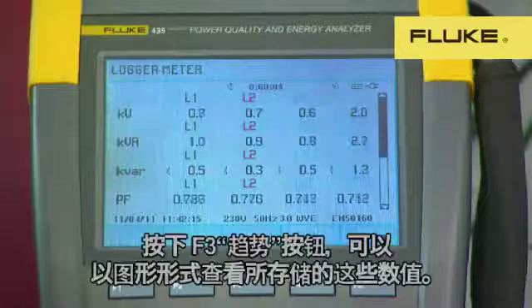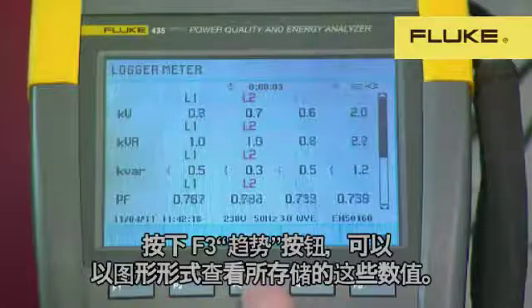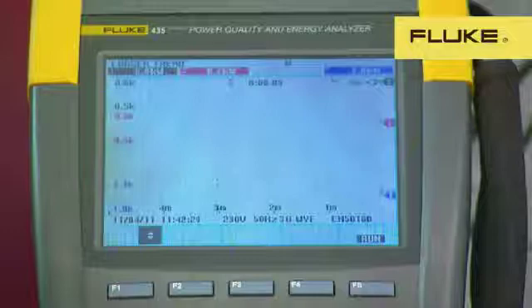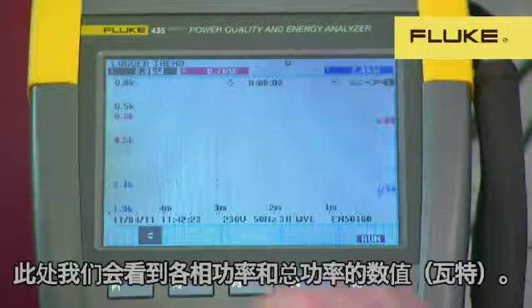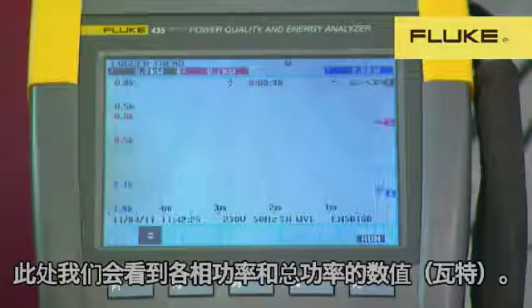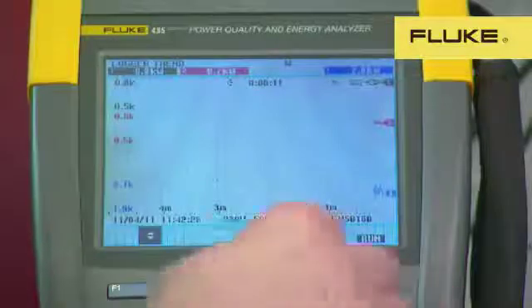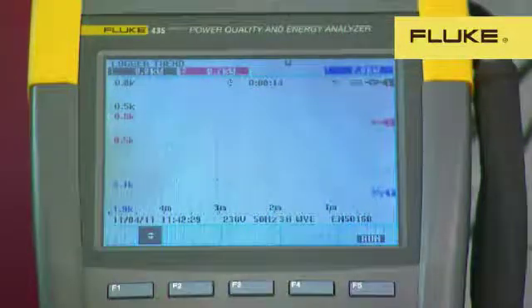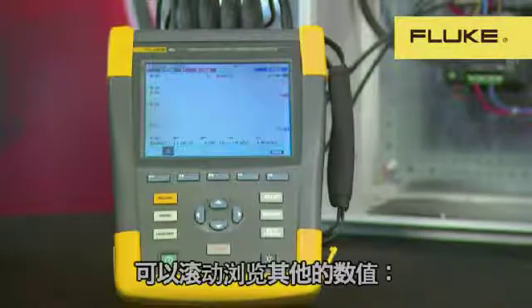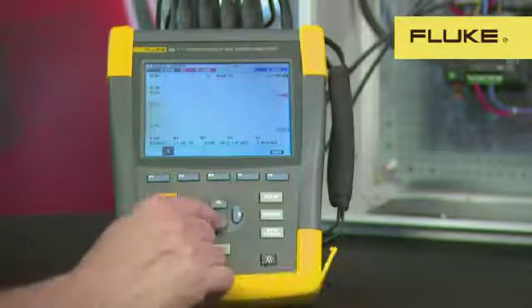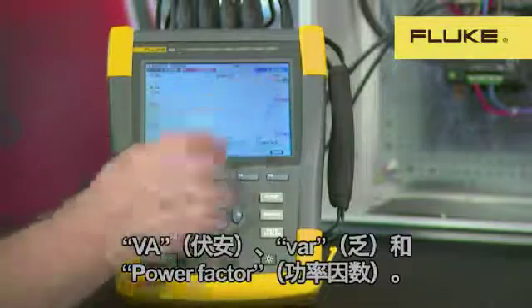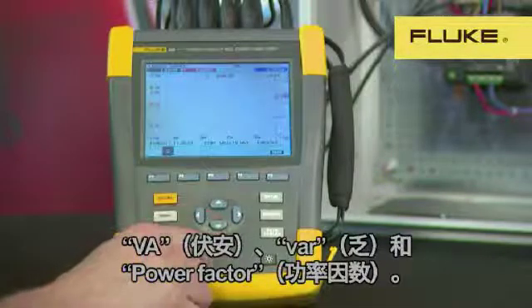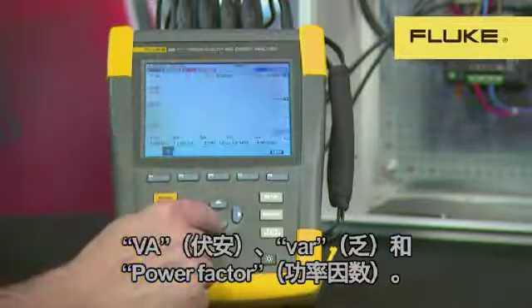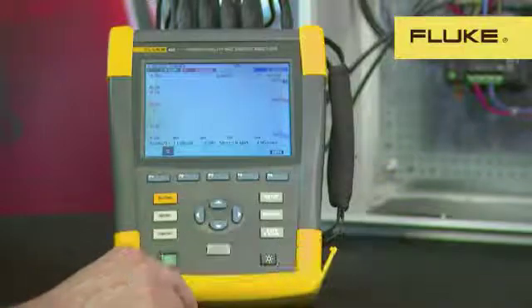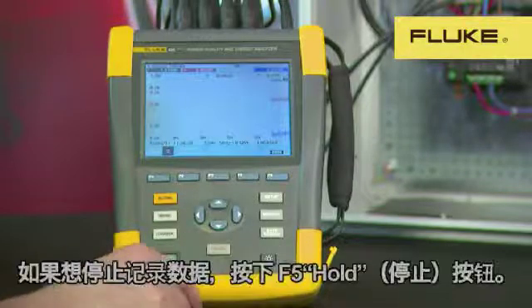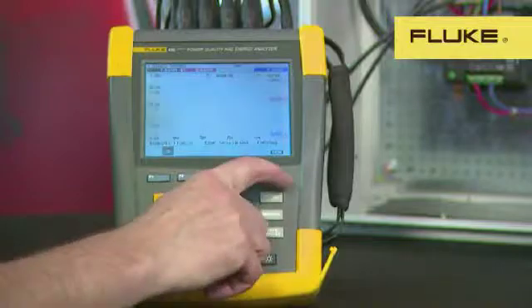These stored values can be viewed as a graph by pressing F3 Trend. Here we can see the power in watts on each of the phases and the total power. We can scroll through to see other values: VA, VAR and power factor. To stop recording, press F5 to hold.